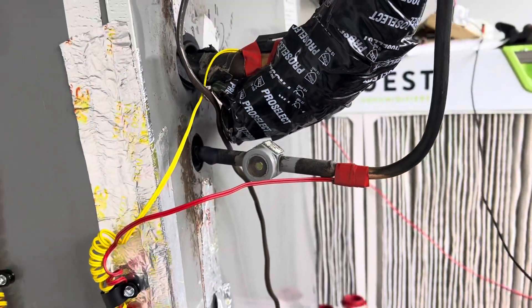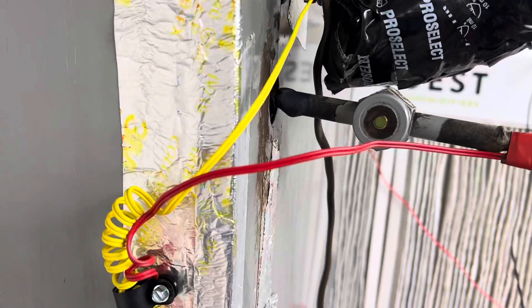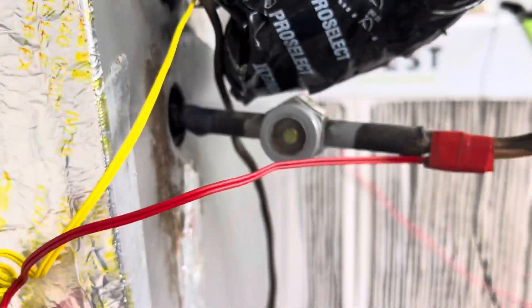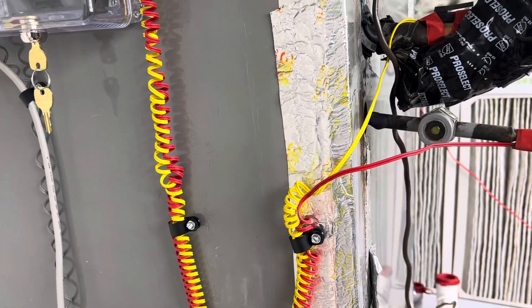What do you see there? This is a sight glass just before the expansion valve. Now I leak checked the shit out of this the other day because I worked on it and did an earlier video. It looks like low refrigerant.